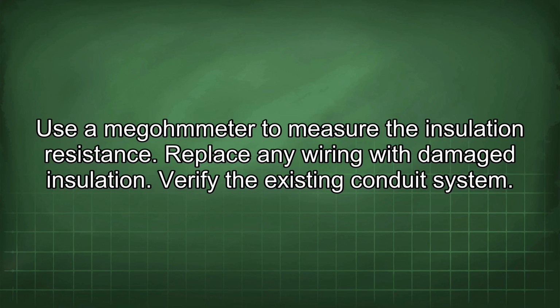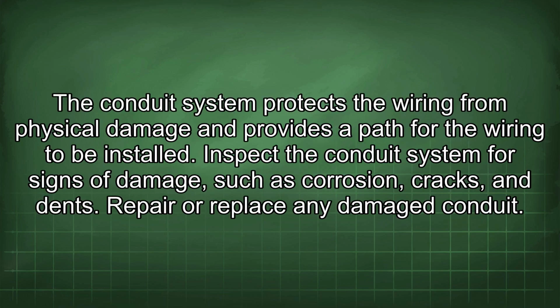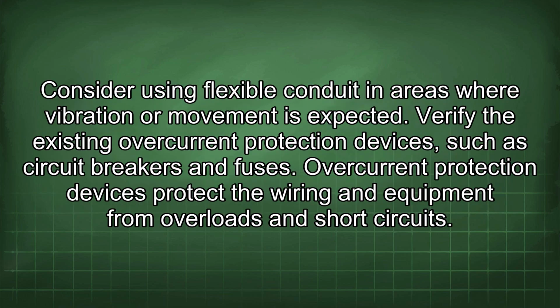Verify the existing conduit system. The conduit system protects the wiring from physical damage and provides a path for the wiring to be installed. Inspect the conduit system for signs of damage, such as corrosion, cracks, and dents. Repair or replace any damaged conduit. Consider using flexible conduit in areas where vibration or movement is expected.